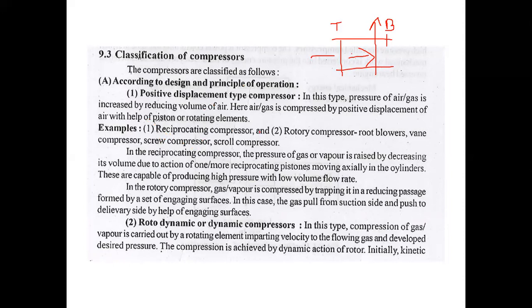For example, reciprocating compressors — generally this type of compressor is used in workshops. Then rotary compressors: lobe compressor, vane compressor, screw compressor, and scroll compressors are the examples. In the reciprocating compressor, the pressure of gas is raised by decreasing volume due to the action of one or more reciprocating pistons moving inside the cylinder. These are capable of producing high pressure with low flow rate. In the lobe compressor or blower, gas is compressed by trapping it in a reducing passage formed by a set of engaging surfaces, and the gas is pushed from the suction side to the delivery side.